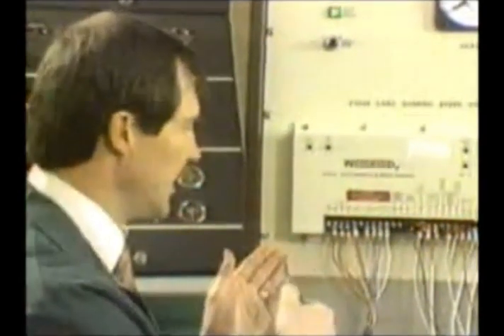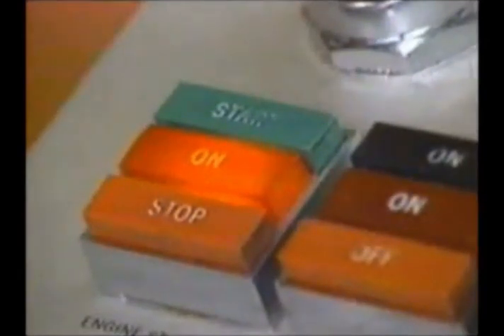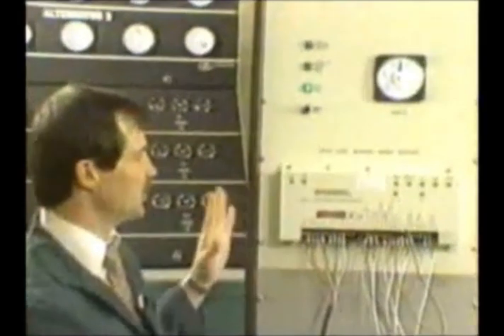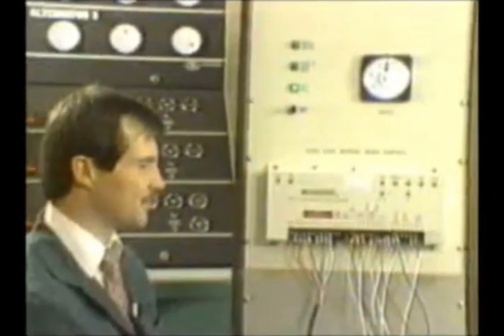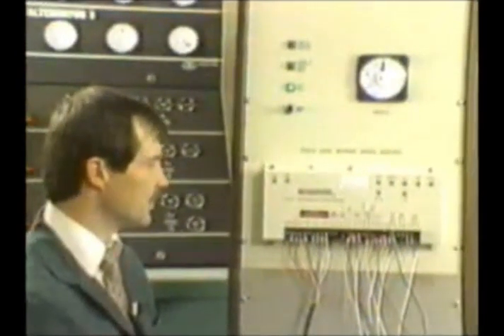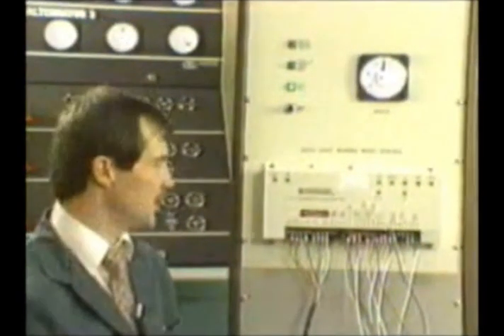If it does, that tells me my CTs were hooked up correctly to begin with, and that I can go ahead and hook up the A phase back to terminal 5 and leave it alone because my CTs will be correct. So let me go ahead and start the unit. Come up to 60 hertz.